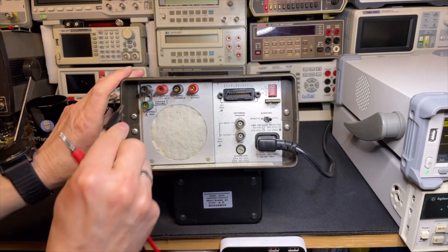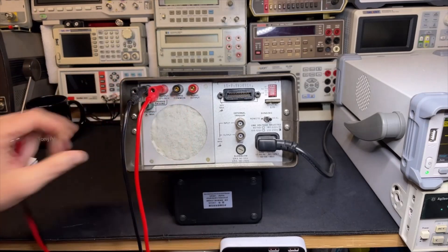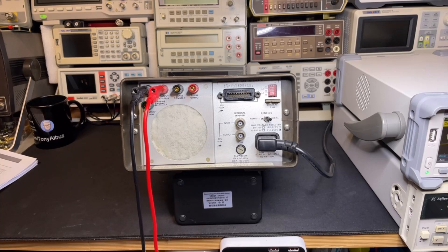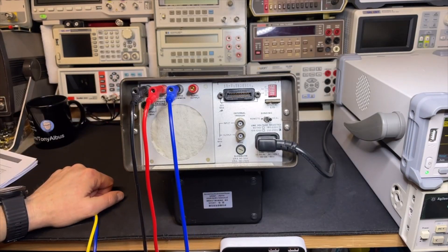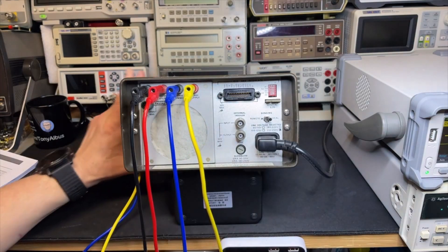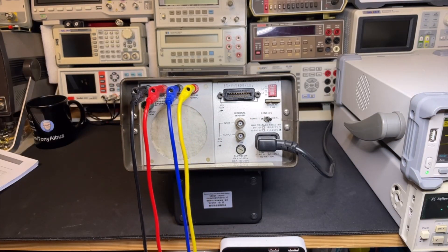So how does that work? Well, we first just connect the normal, the positive and the negative wires. And then for the sense, I usually pick other colors that they also need to make sense. So I have here the darker one. That is the sense for the low. And here I have the sense for the positive.